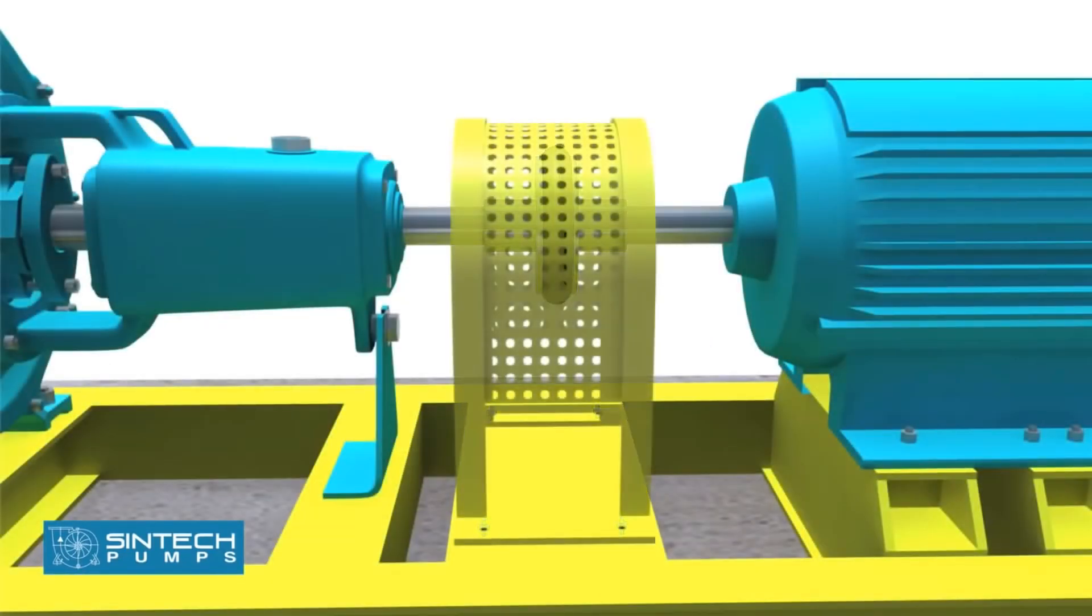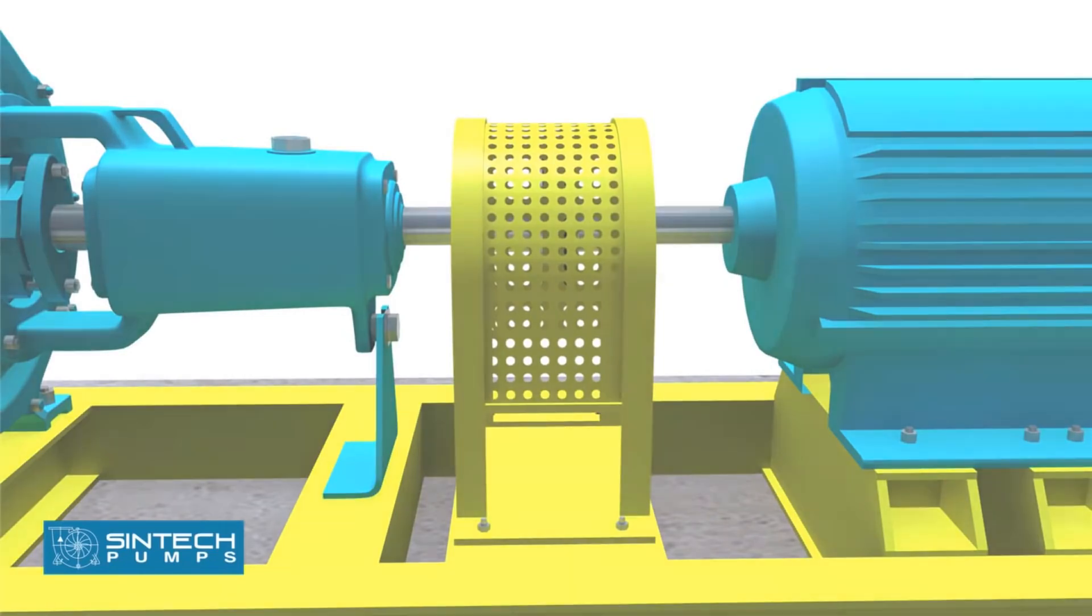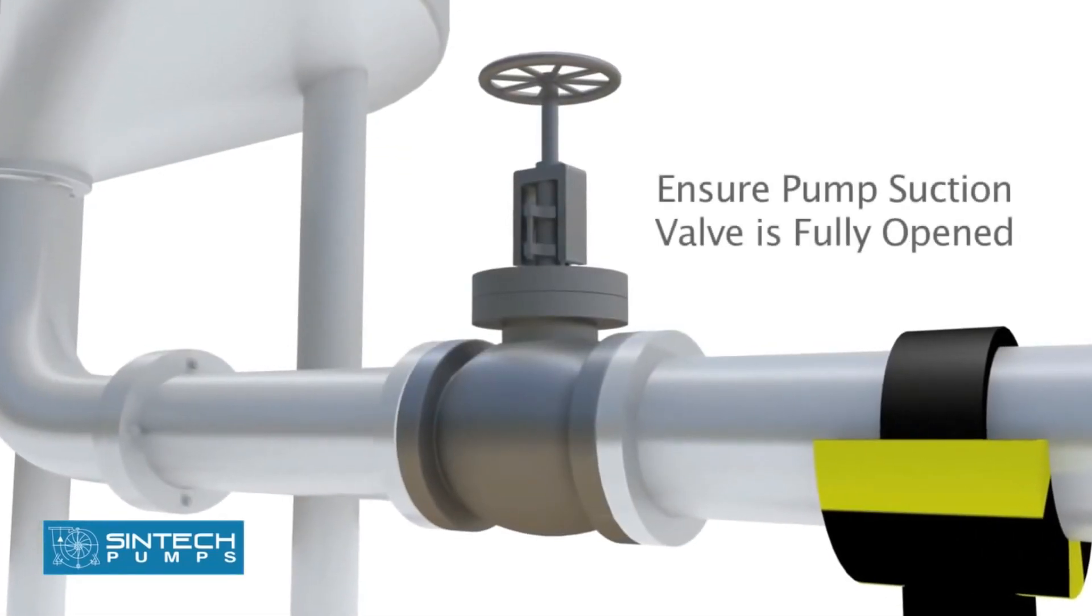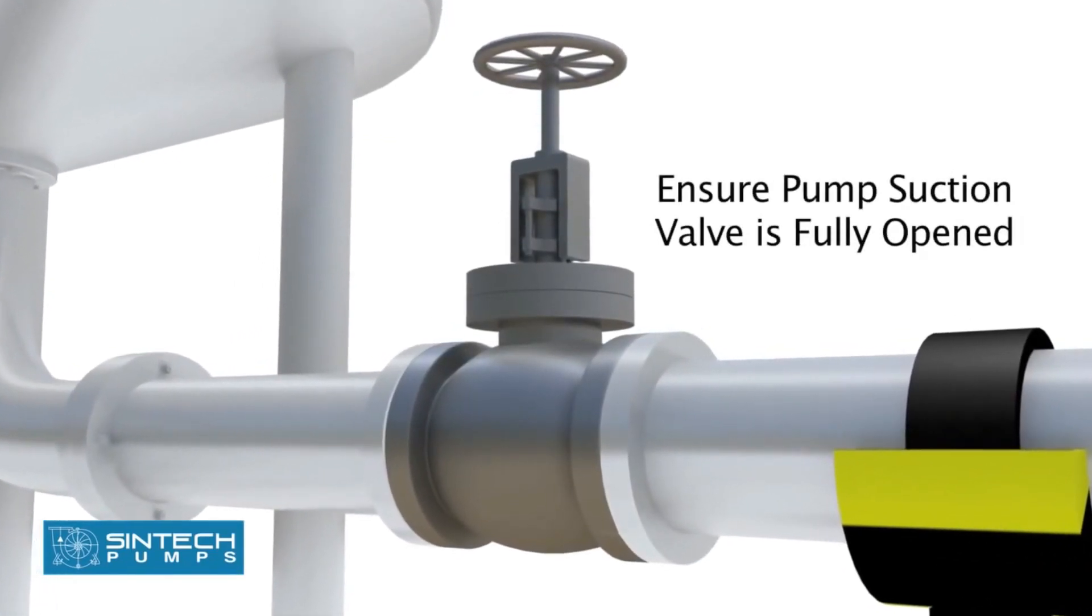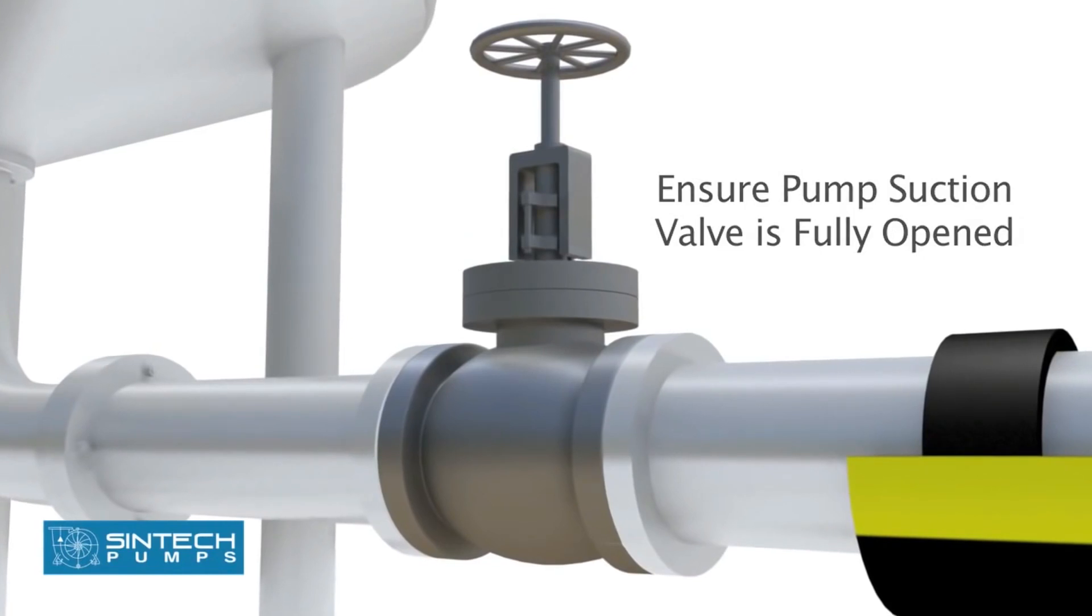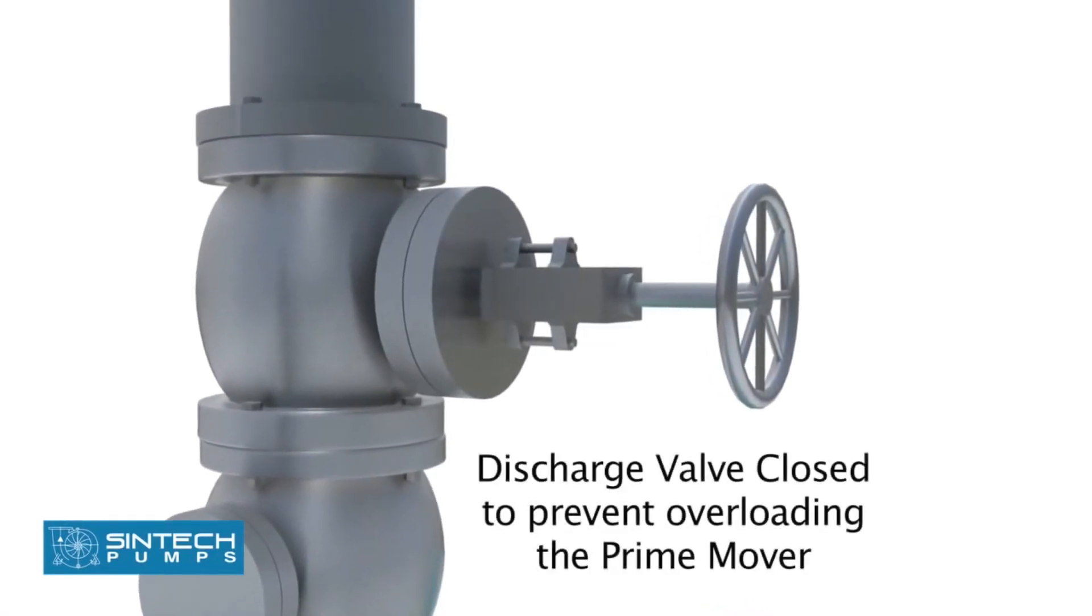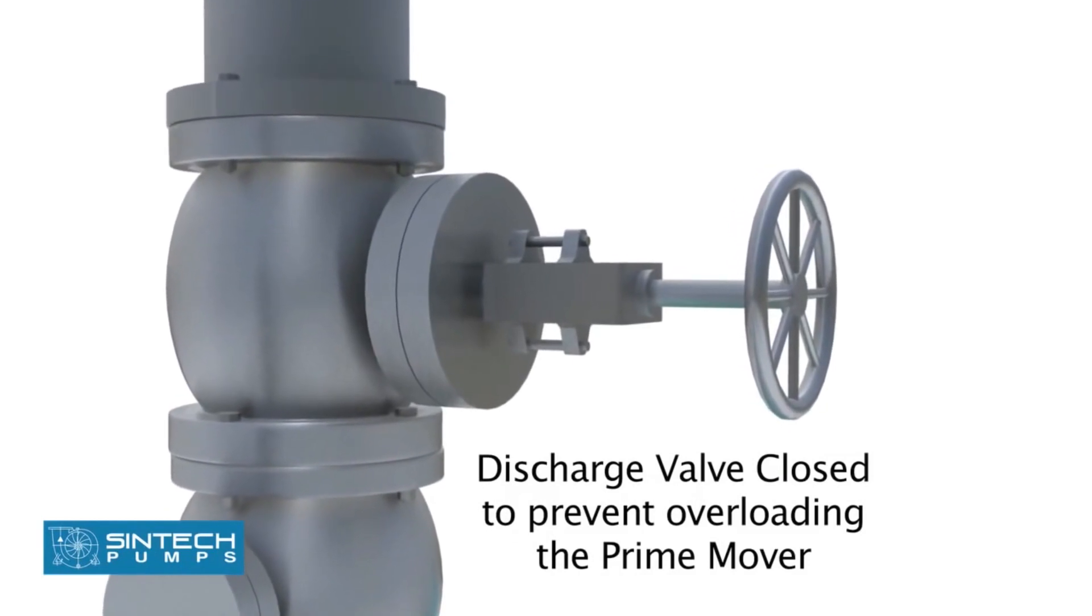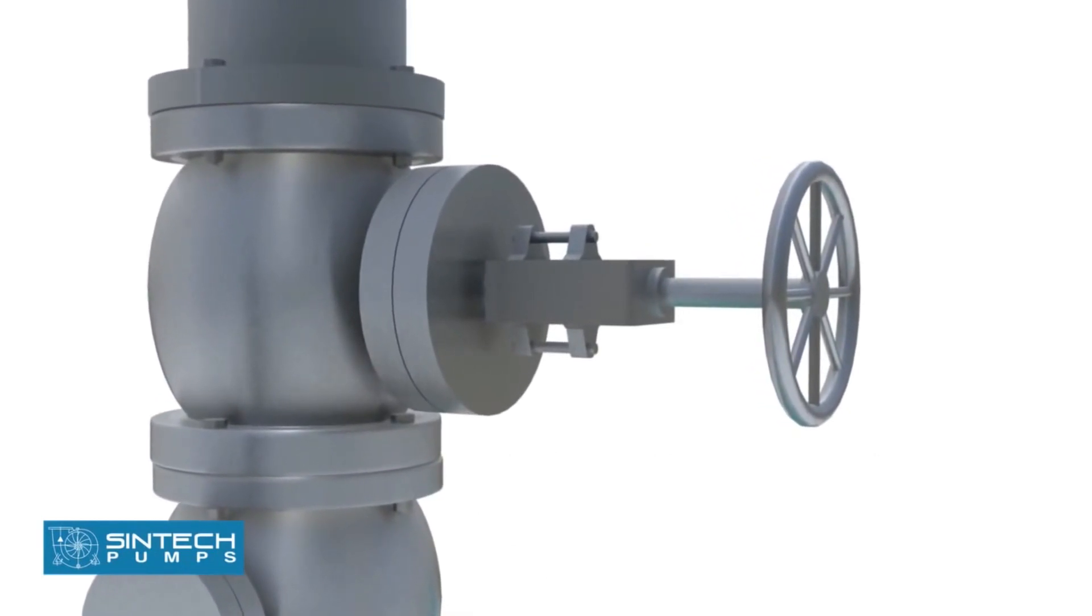Place the coupling guard and tighten the bolts. Ensure that pump suction valve is fully opened and all joints are checked for any leakage. The opening of discharge valve is kept closed as this prevents overloading the prime mover.